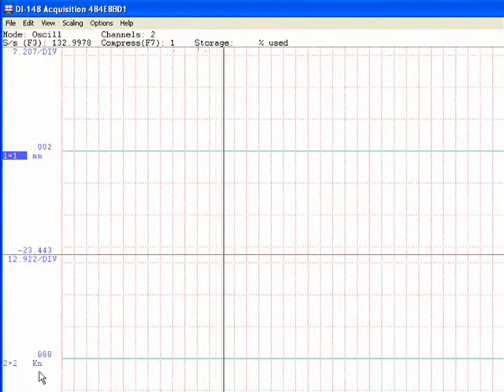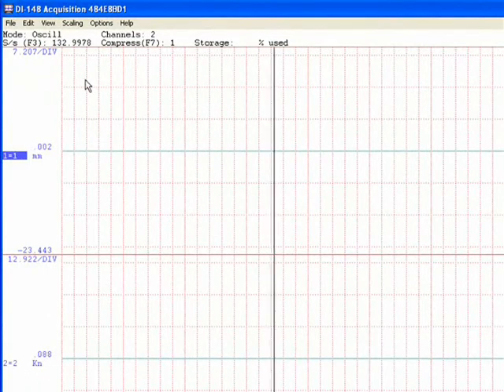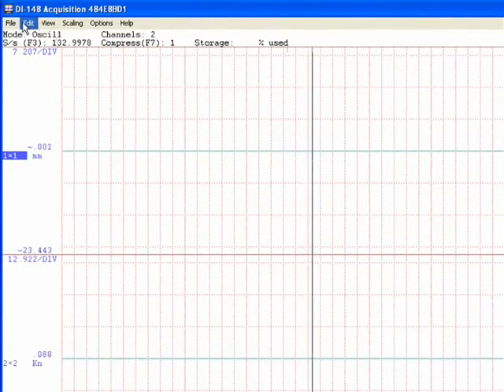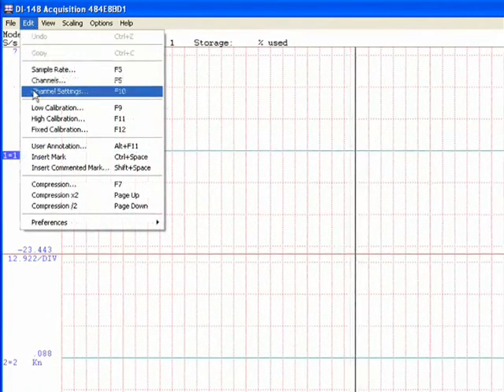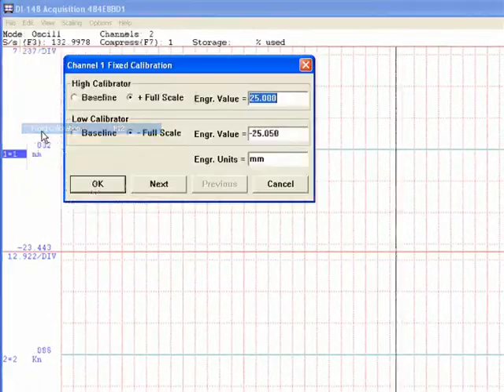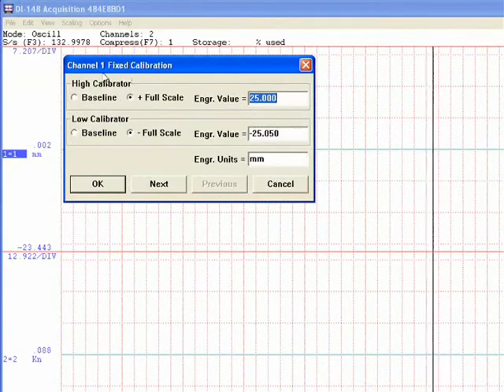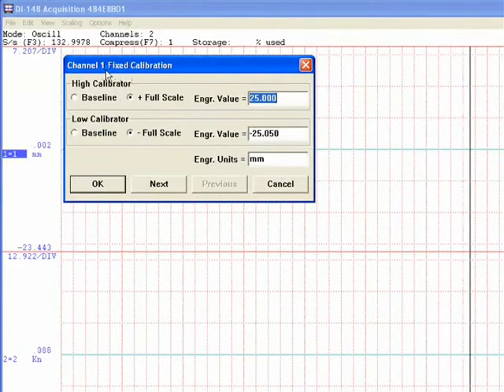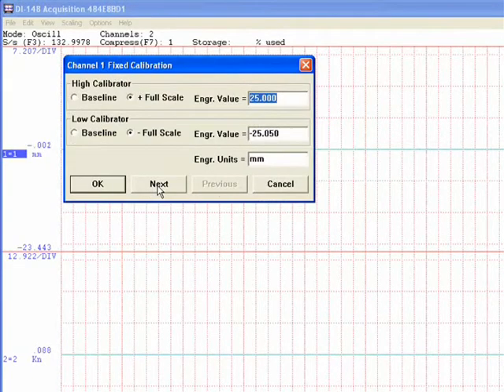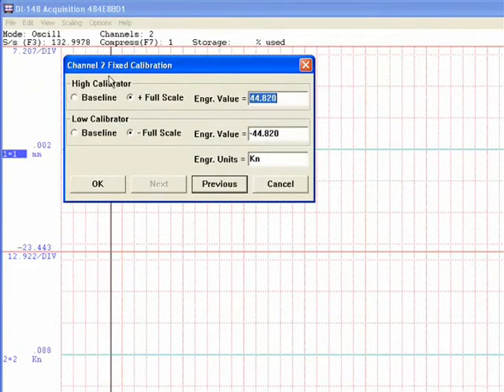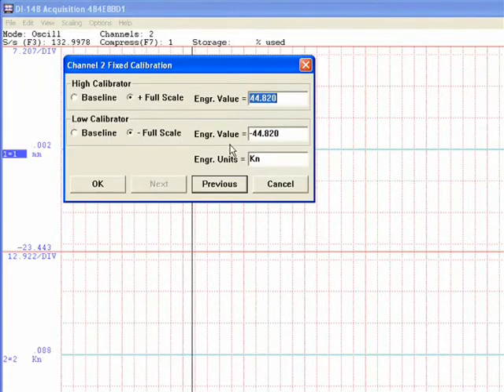Now, we're going to address the Load. Edit, Fixed Calibration. You want Transducer 2, Full Scale. Now, what I'm going to do is change this because I already know what it should be.